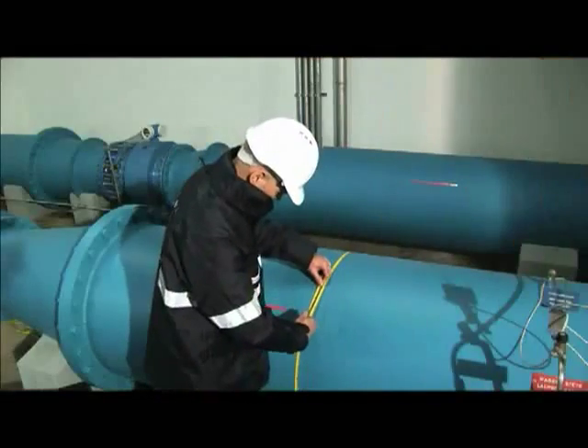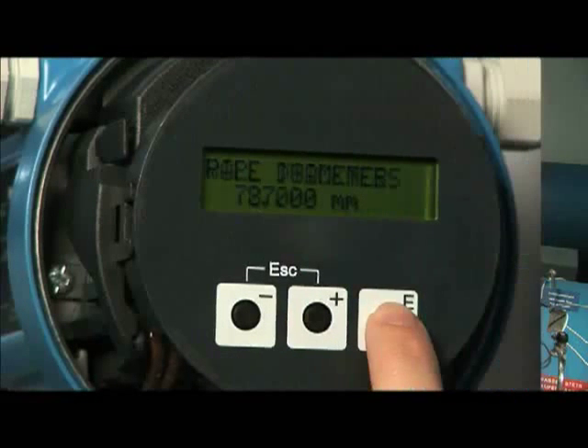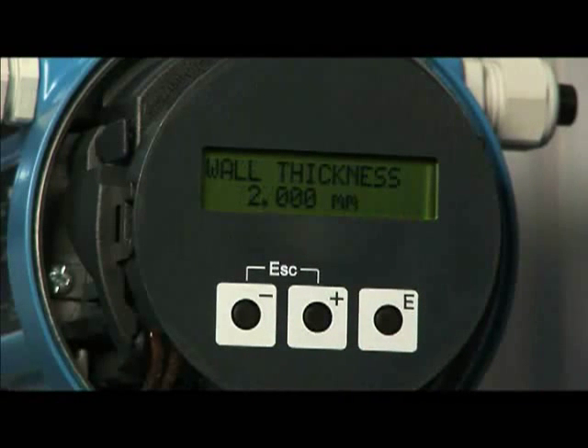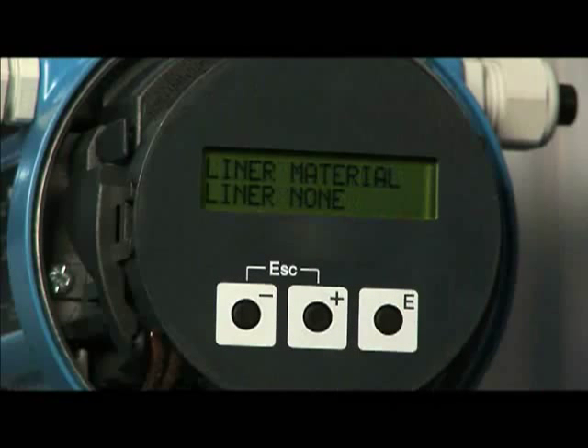If the pipe diameter cannot be found, we suggest measuring the circumference of the pipe and entering that value. Now enter the pipe wall thickness. If this is unknown, it is possible to estimate the value.